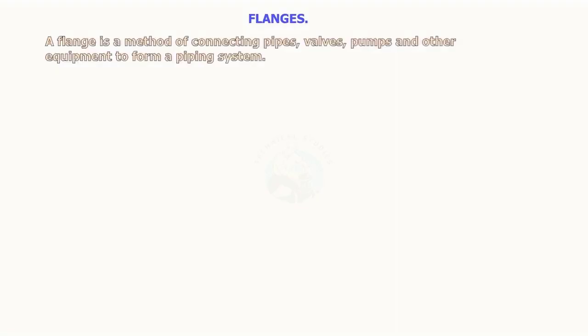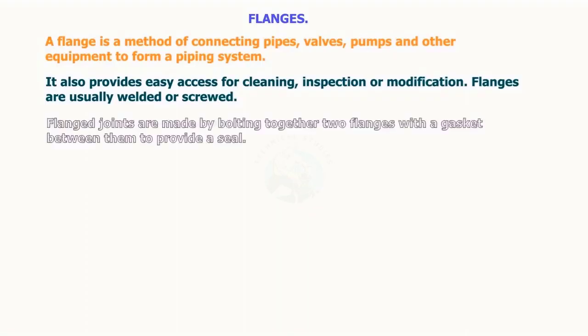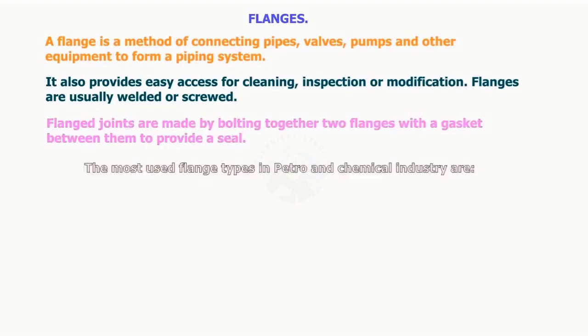A flange is a method of connecting pipes, valves, pumps, and other equipment to form a piping system. It also provides easy access for cleaning, inspection, or modification. Flanges are usually welded or screwed. Flange joints are made by bolting together two flanges with a gasket between them to provide a seal. The most used flange types in the petro and chemical industry are listed as follows.